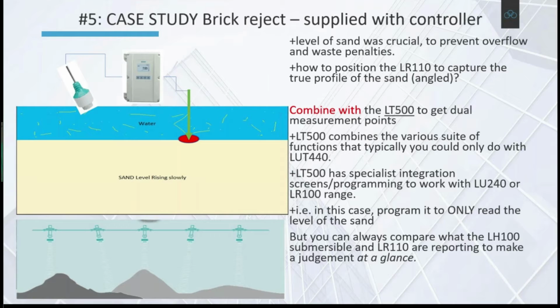The beauty of the LT500 is that you can take in any 4 to 20 milliamp level transmitter, whether submersible or a DP cell using pressure to work out the level, and combine it into the LT500. It has special screens tailor-made for integration with the LR100 range and the LU240, the ultrasonic non-contact level probe.